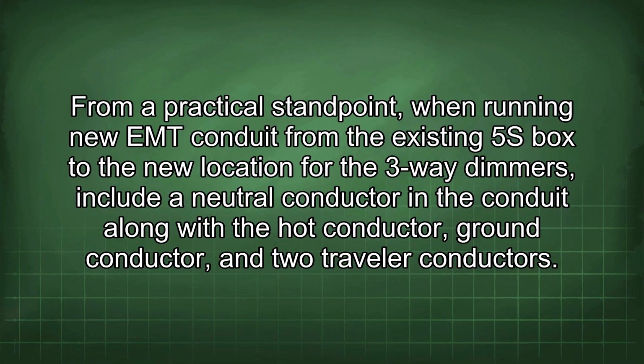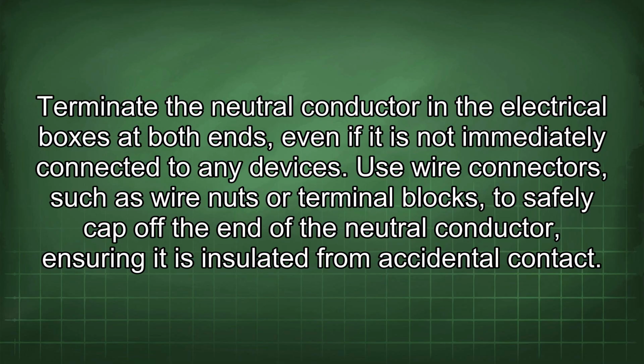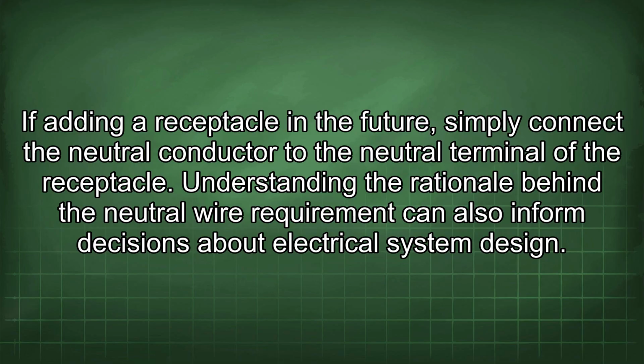From a practical standpoint, when running new EMT conduit from the existing 5S box to the new location for the three-way dimmers, include a neutral conductor in the conduit along with a hot conductor, ground conductor, and two traveler conductors. Terminate the neutral conductor in the electrical boxes at both ends, even if it is not immediately connected to any devices. Use wire connectors, such as wire nuts or terminal blocks, to safely cap off the end of the neutral conductor, ensuring it is insulated from accidental contact. If adding a receptacle in the future, simply connect the neutral conductor to the neutral terminal of the receptacle.